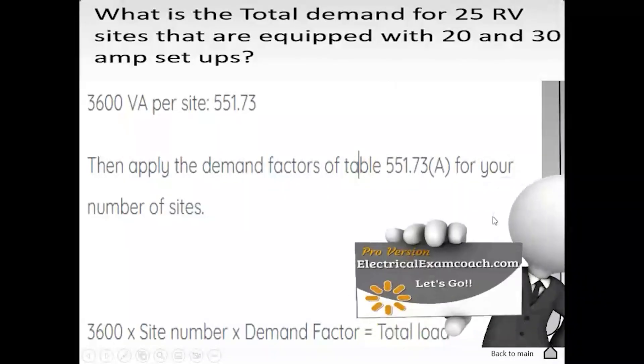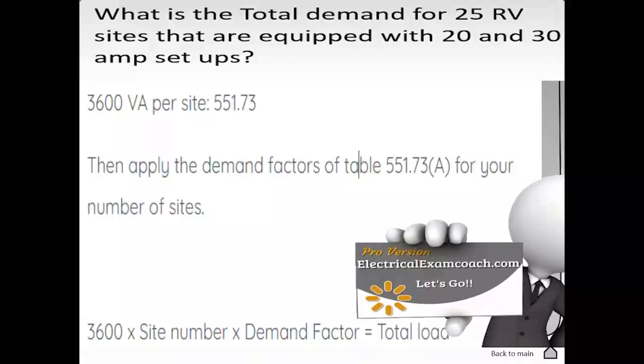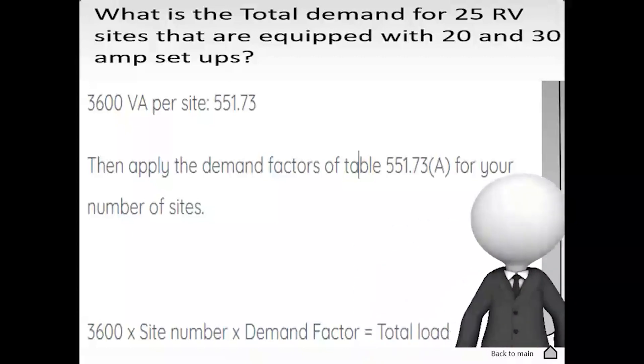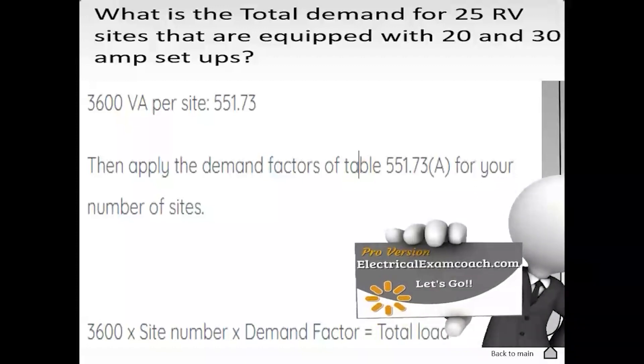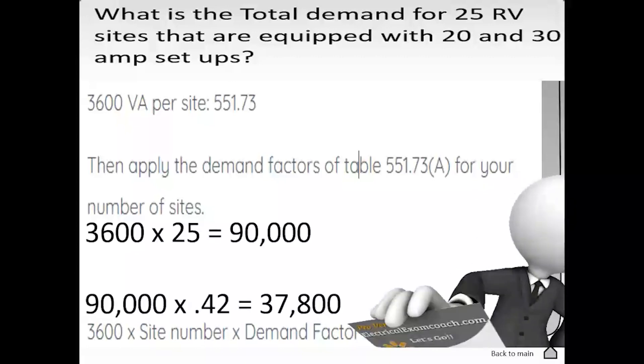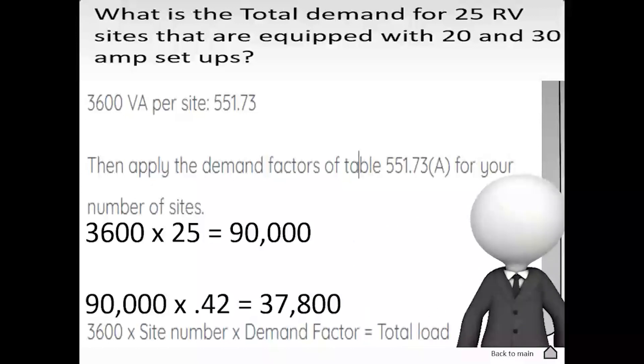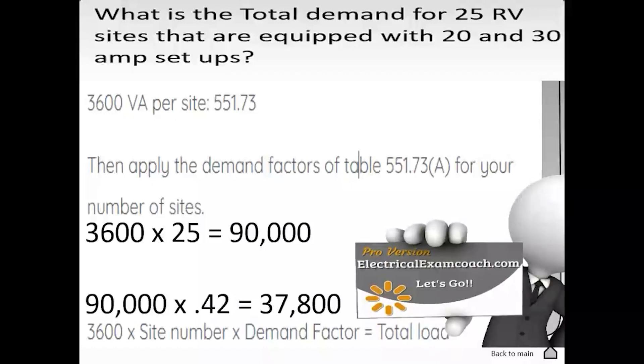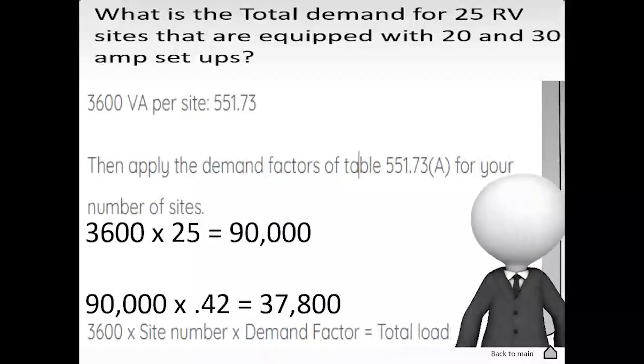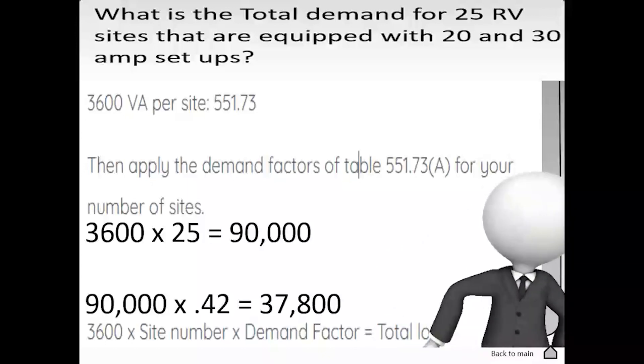To find this one, we're going to head to 551.73. It's going to let us know for RV sites that are equipped with a 20 and a 30 amp setup that you have to calculate it at a minimum of 3,600 VAs per site. But we can't stop there. We have to head to the table and we can actually apply a demand factor for this load. So we take our 3,600 per site, multiply it by our 25 sites and that gives us 90,000 VAs. Now we can go down to our table and check the demand factor for 25 and it ends up being 42%. So we take our original load multiplied by our demand factor and that gives us a new reduced load of 37,800. Great job.